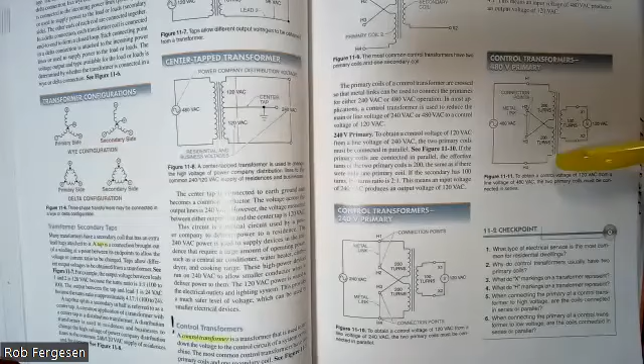So if I put my continuity check, my ohm meter across one coil, and I get 0 or very, very low resistance, low ohms, then that means that something's shorted out. And what I should get is the specified ohms across that coil. And if I put my resistance meter across there, I should get the specified resistance across that coil. Each coil is going to have a specified resistance that you should be able to look up on a particular transformer.